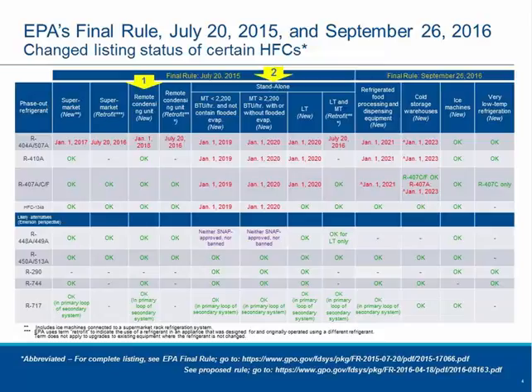Some of these refrigerants are, in fact, non-flammable A1s, as well as flammables like R290, which is propane. So as you can see here, we have a couple of things that we need to pay attention to. On the remote condensing unit side, we have a 404A delist, but 407A is, in fact, okay to use, in addition to 134A. 404A is a medium back pressure refrigerant. It is a great refrigerant in terms of performance and capacity as it relates to medium temp and low temp applications. 134A is a great refrigerant used for medium temp applications.